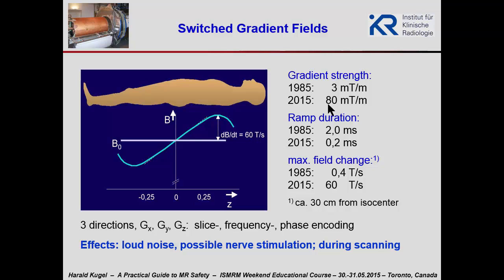And you see that, while during the last 30 years the magnetic field strength remained about the same, between 1.5 Tesla, 4 Tesla in early years, 3 Tesla now, in contrast to this, the maximum attainable gradient strength and ramp durations changed quite a lot. In 1985, we started with 3 millitesla per meter. Today, we are at 80 millitesla per meter. They became also faster. Ramp duration was 2 milliseconds in earlier days and 0.2 milliseconds today.